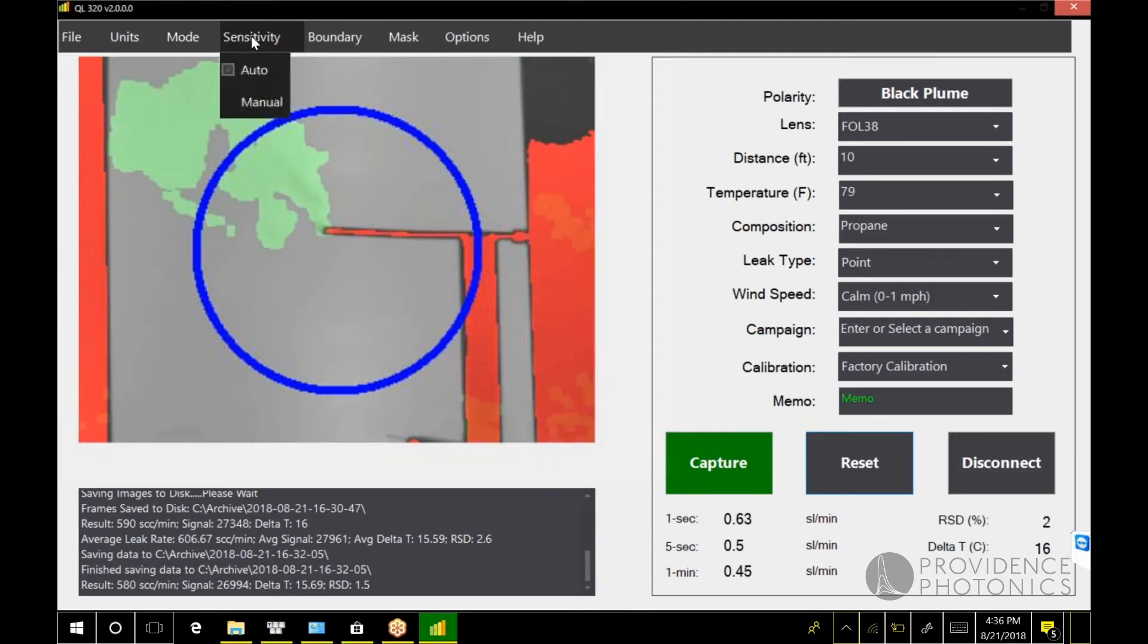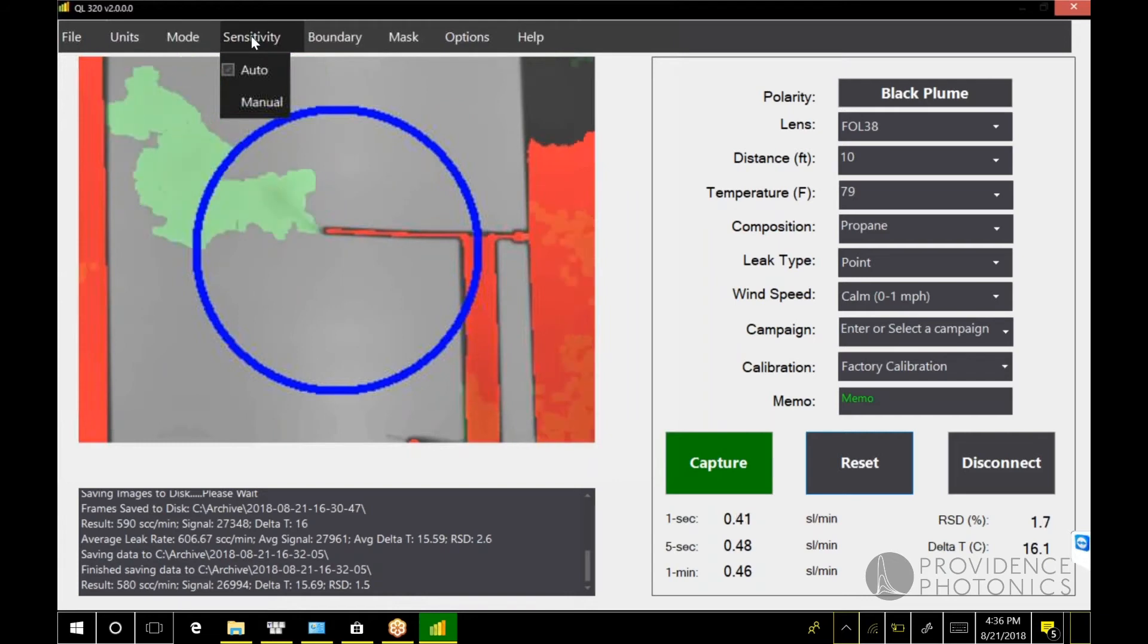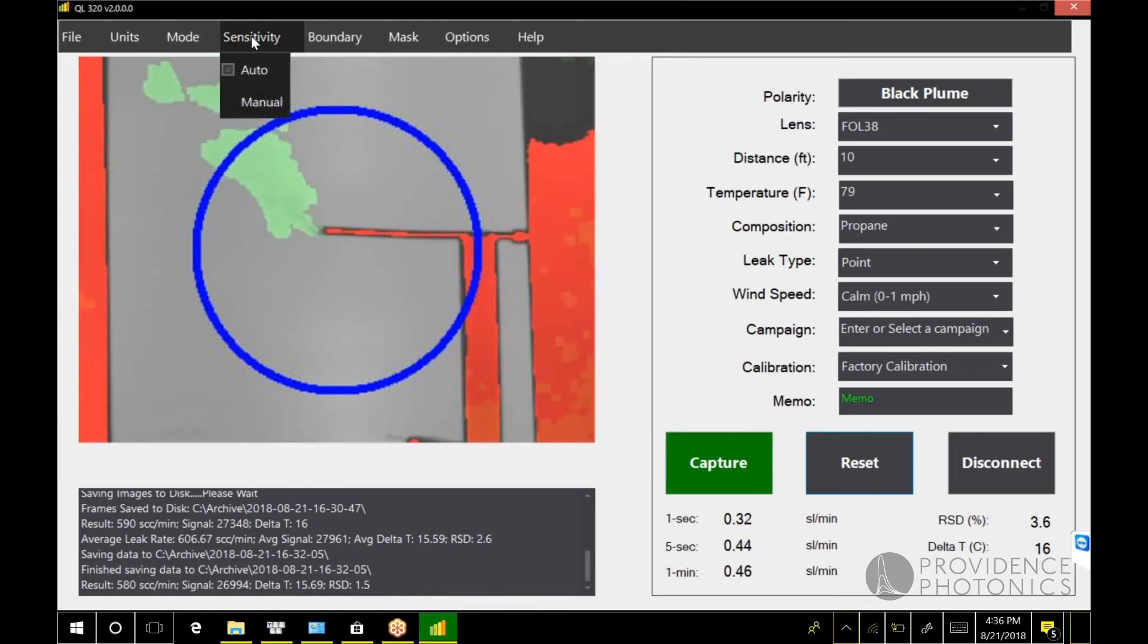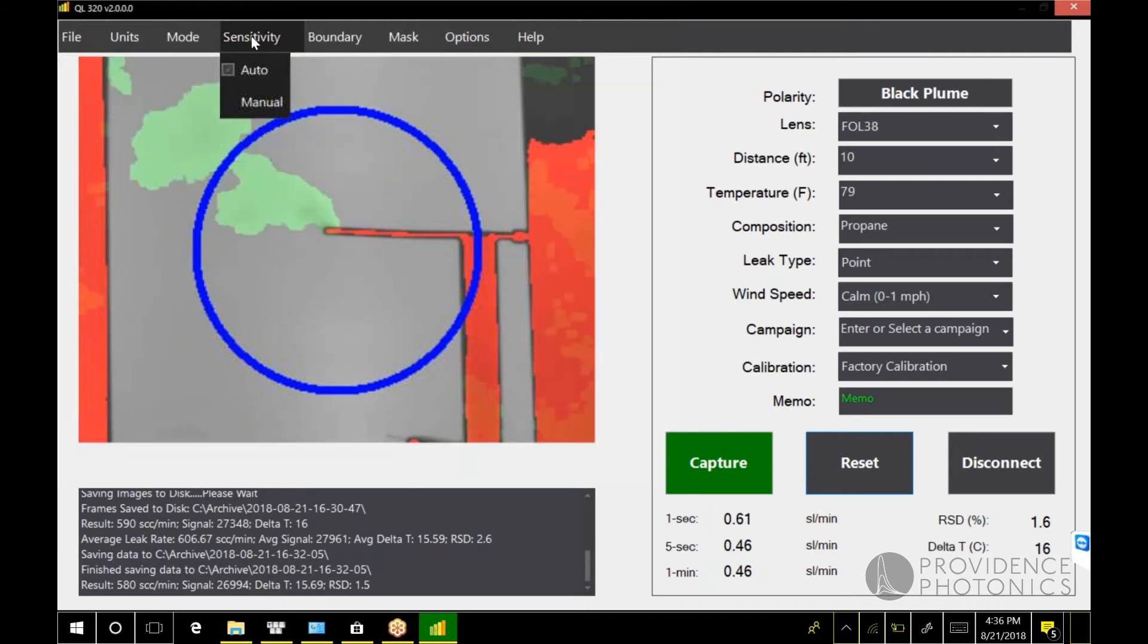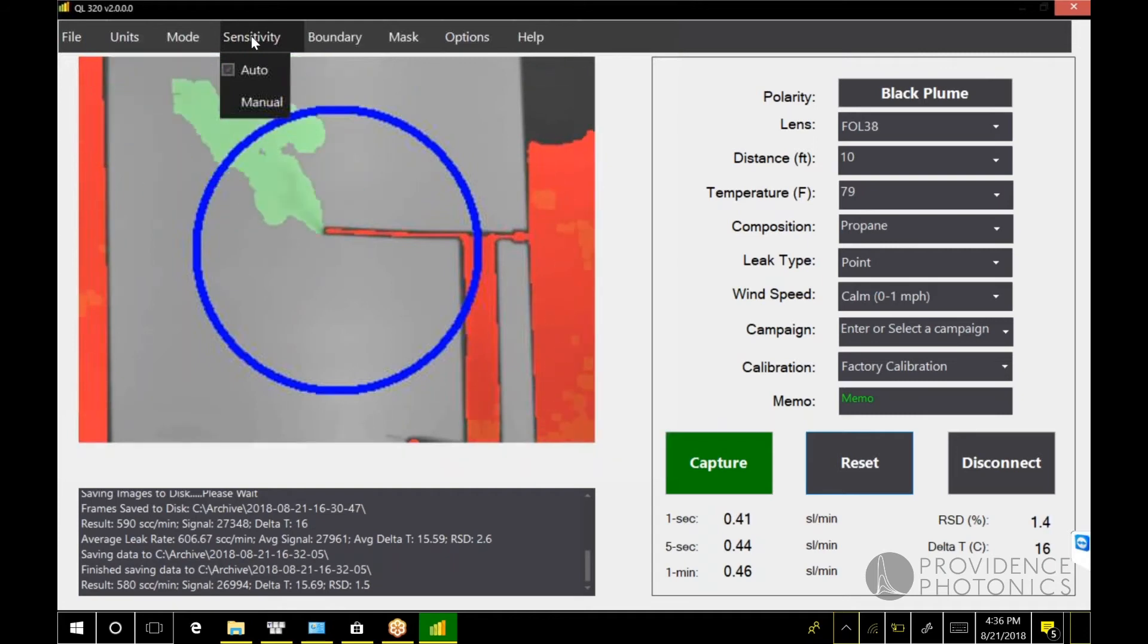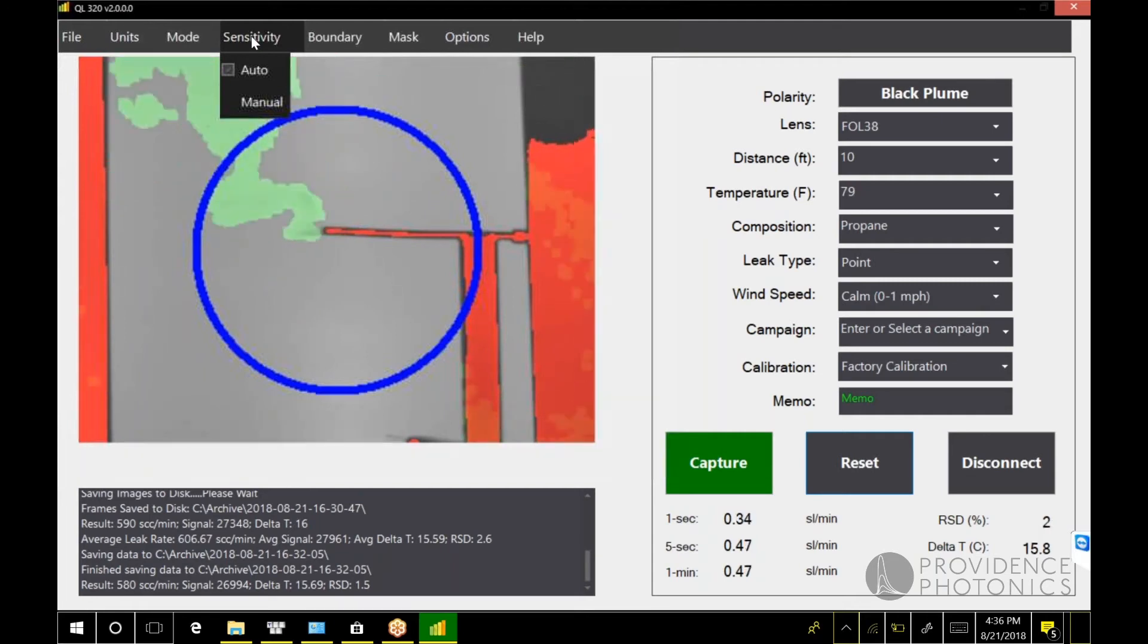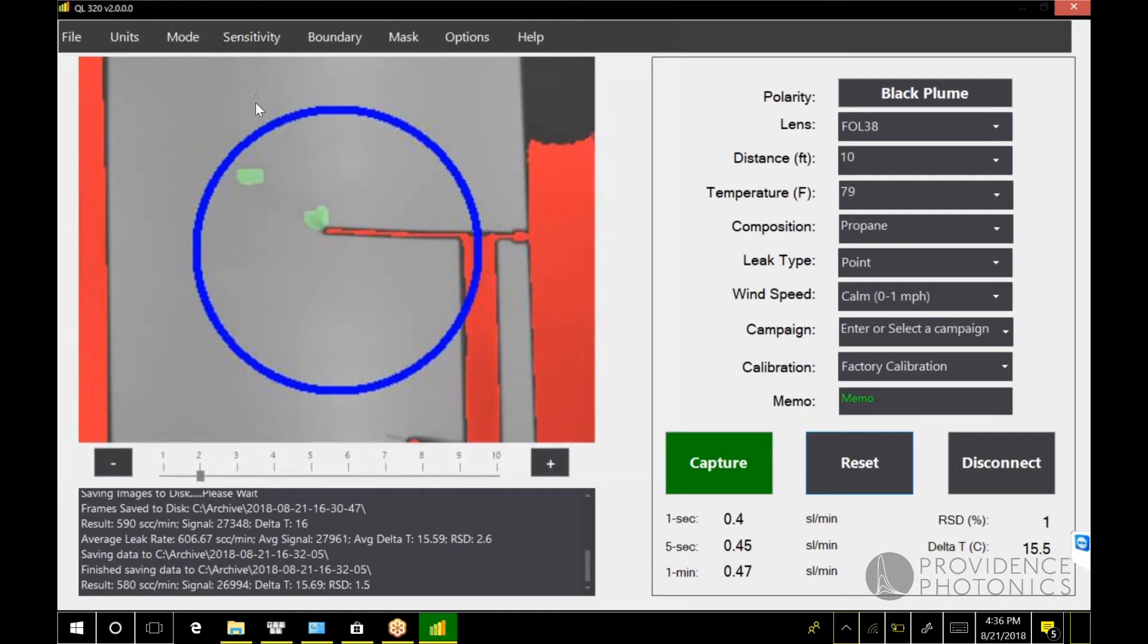One new feature of version two is a new control which gives you more options for setting the sensitivity of the plume extraction. Right now we're running in auto mode where the QL 320 algorithm is determining what threshold to apply to separate the plume from the background. But if you run into a situation in the field where either you're not getting all the plume extracted or maybe you're getting too much, you have too much noise in there, you have the option to switch to manual sensitivity mode.